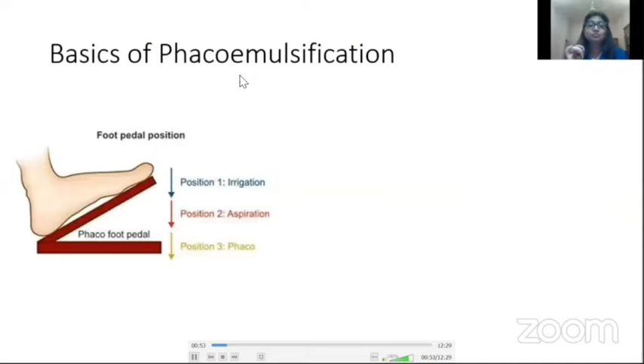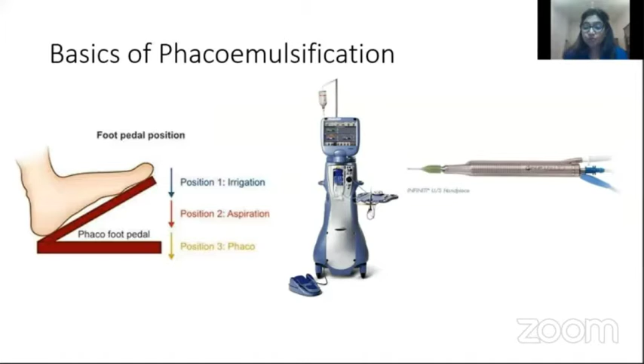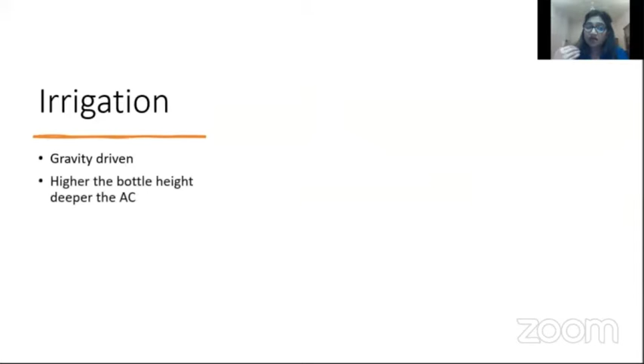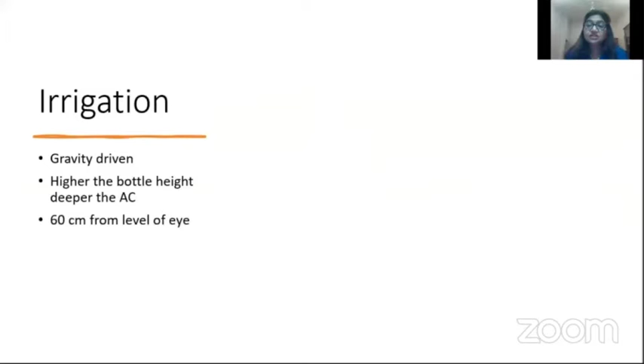Be it any machine, whether a basic one or the most advanced one, these 3 elements form a good phacoemulsification. For this, we have a handpiece connected to the irrigation and aspiration tubings, and it has an electrical connection for providing the phaco power. Now, irrigation is gravity driven, because the higher the bottle height, the deeper the anterior chamber, and it is usually 60 centimeters from the level of the eye.